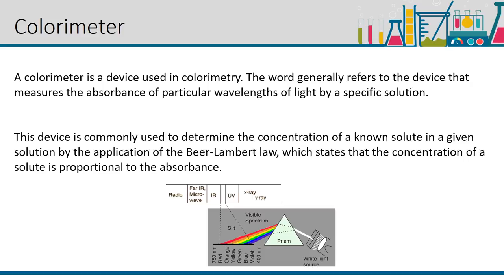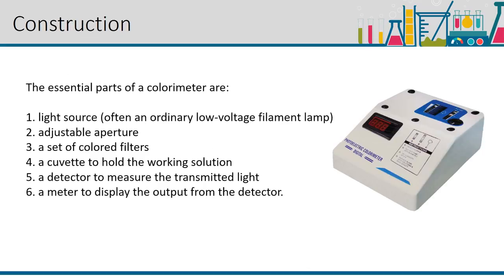The essential parts of a colorimeter are: 1. light source, often an ordinary low voltage filament lamp; 2. adjustable aperture; 3. a set of colored filters; 4. a cuvette to hold the working solution; 5. a detector to measure the transmitted light; 6. a meter to display the output from the detector.